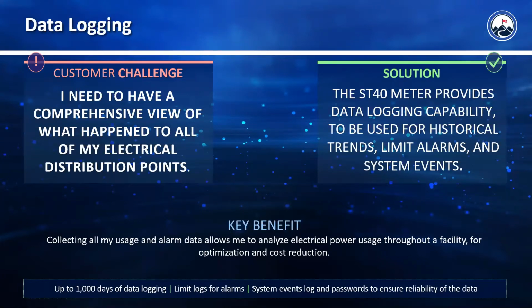So to really have a comprehensive view of what is happening in all of your electrical distribution points, it's really critical that you be able to view data over a period of time. And this meter has the full data logging capabilities for historical trending, limits, alarms, and system events. And it can actually provide you up to 1,000 days of data logging. So you can go years without even taking up the entire memory of the meter. And this 1,000 days of logging will include your energy information, your power quality information, your limit logs. And so if you analyze your data over time and then look at your usage and also your alarm data, you can actually analyze your power usage throughout a facility, and then you can optimize and do cost reduction based on that.